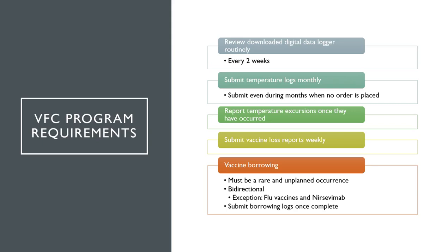Review downloaded digital data logger data routinely every 2 weeks. This has really helped our providers be able to catch temp excursions that they may have missed for some reason, such as an alarm that didn't go off. So if you review the DDL data, you can see and address the issue as it occurs.